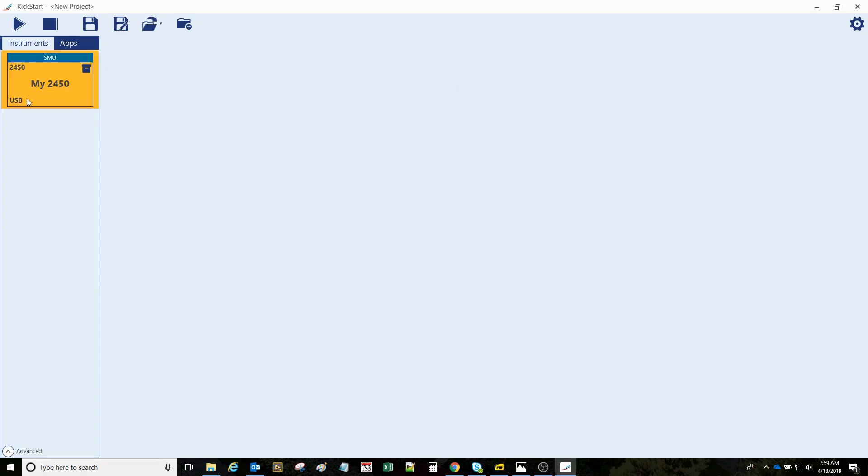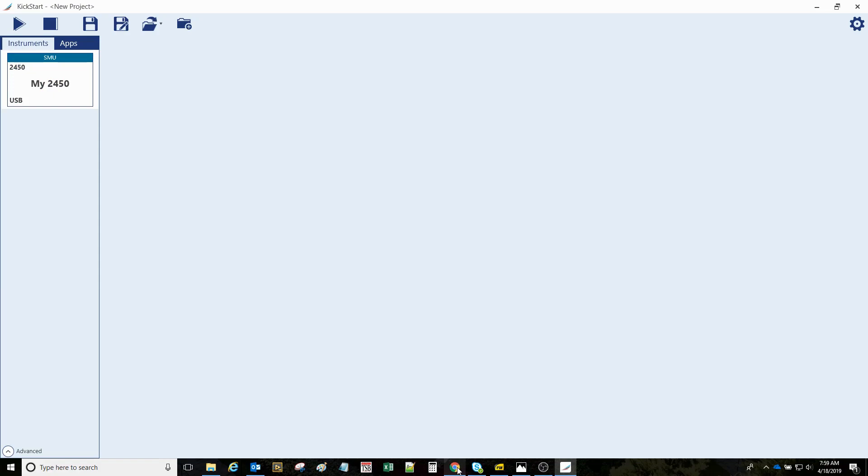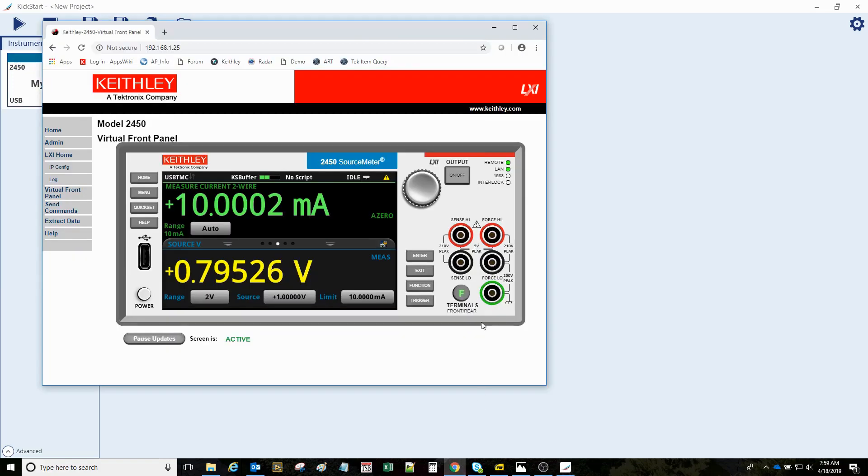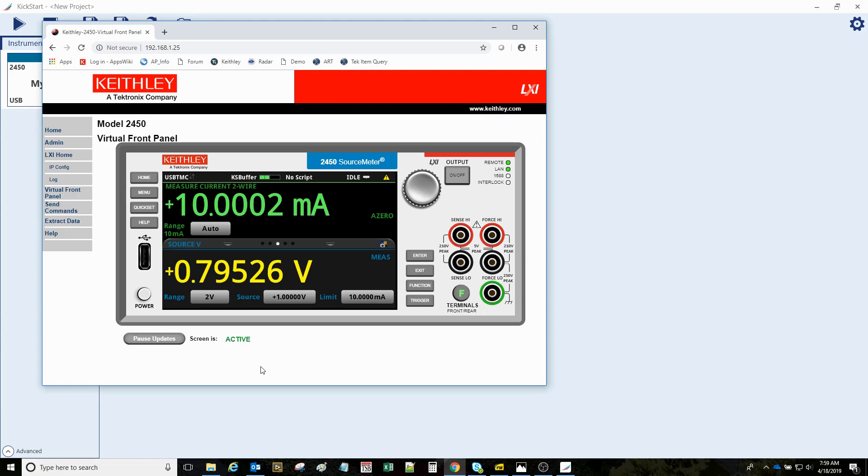As you can see here in the kickstart instrument screen, it has detected the presence of the 2450 on a USB connection. Just as an aside, I simultaneously have a LAN connection at this IP address, and I'm able to bring up this virtual front panel. We'll look at that again here in a few minutes.